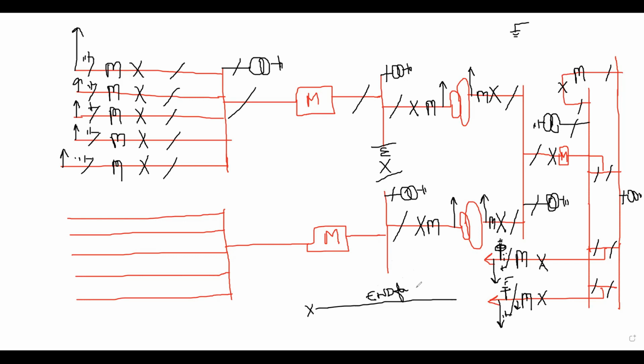So to avoid this condition, we place the CT before the breaker. If any fault occurs between the CT and the breaker, the CT senses the fault, and if it is a zone 2 fault for the upstream breaker, it gives the command to the bus bar differential protection, and all the breakers connected to the bus will be opened. I will talk about this in the distance scheme. Maybe you are not able to understand it yet. I will talk about the CT's position in the control and protection chapter. For the time being, let's assume the CT can be placed on either side of the breaker.